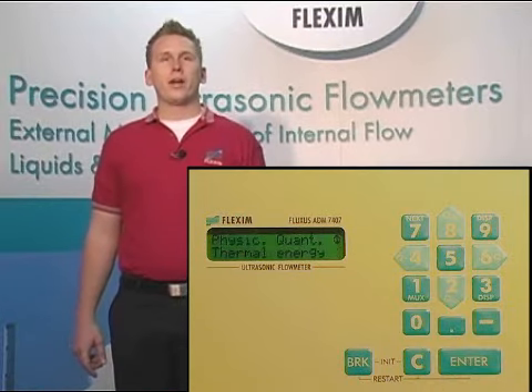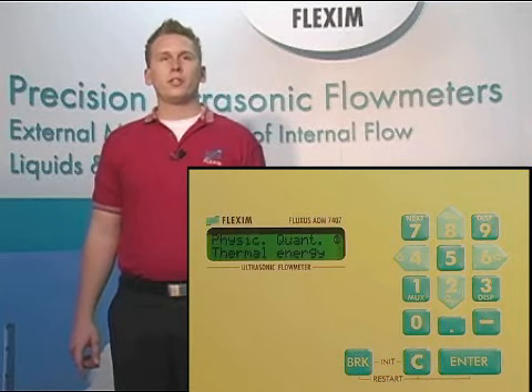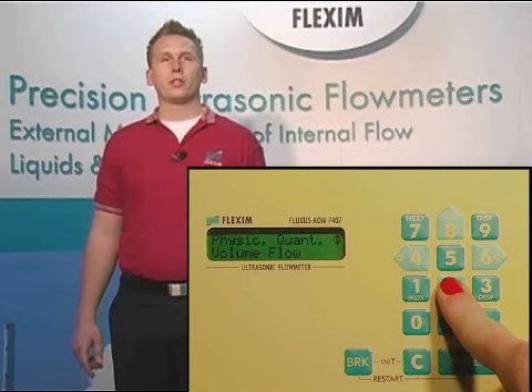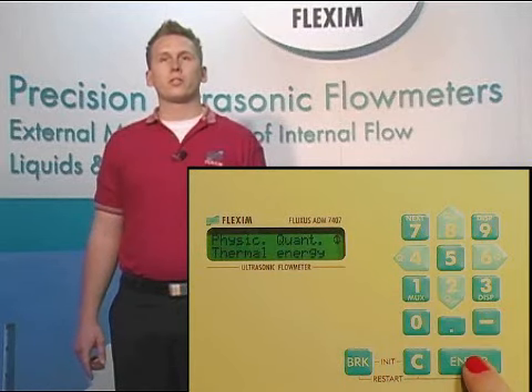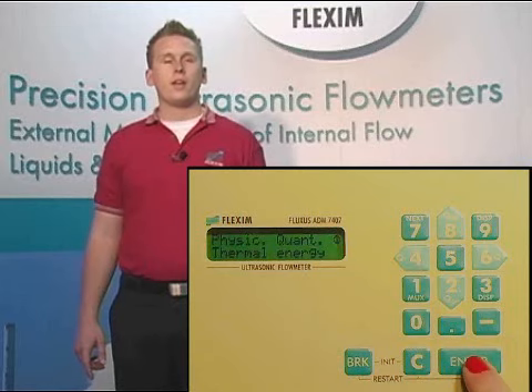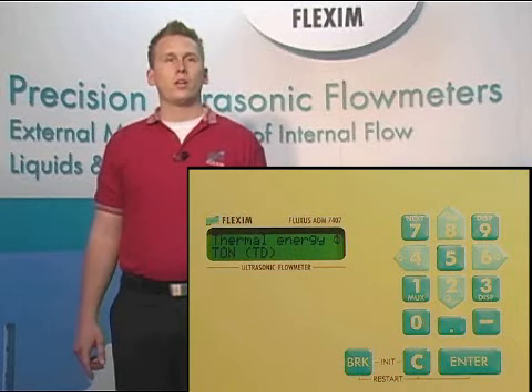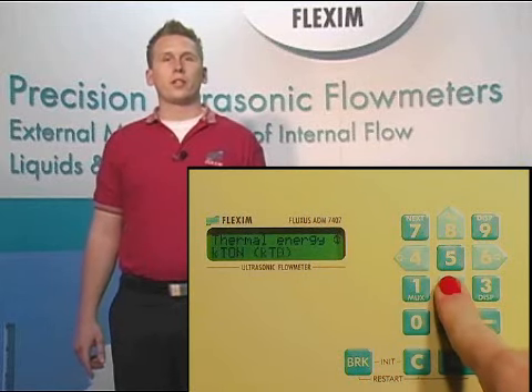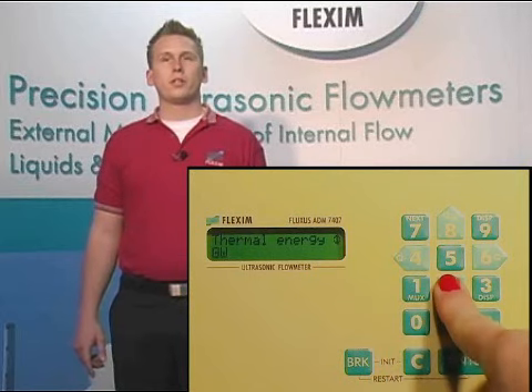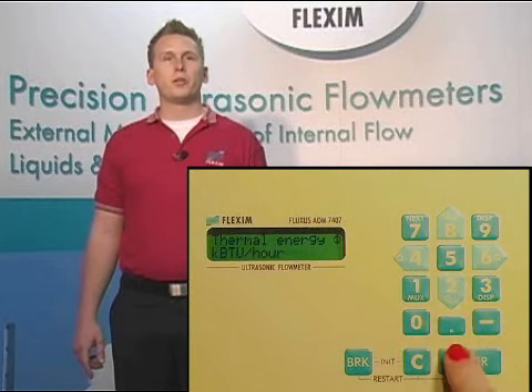The next option we have is the physical quantity we want to measure. We can choose between thermal energy, volume flow, flow velocity, mass flow, or sound speed. So let's choose thermal energy to output the rate of energy usage for our system to the screen for channel A, and hit enter to confirm. Now we need to pick the unit we like to see. We could choose tons or BTU. For now though, let's choose BTU as our unit and hit enter to confirm.